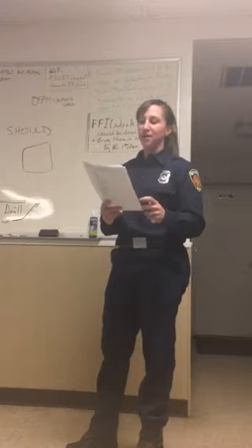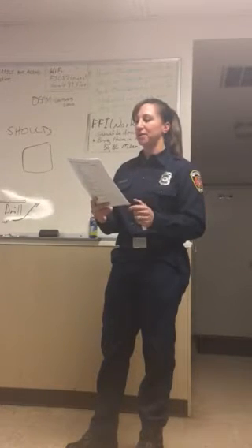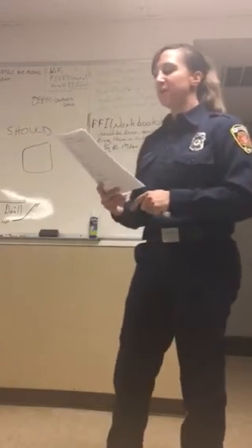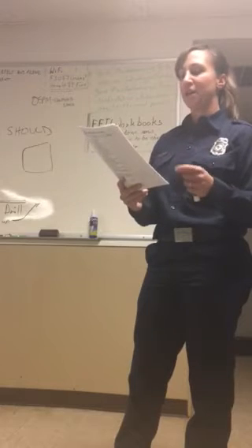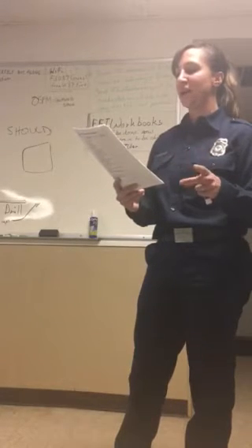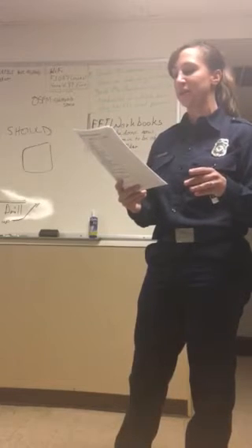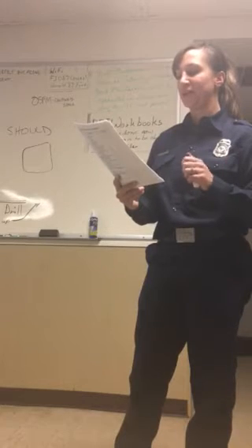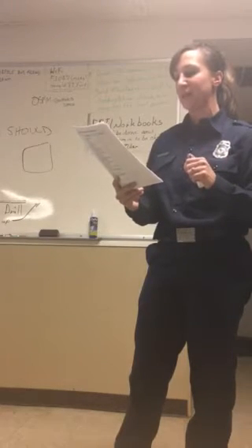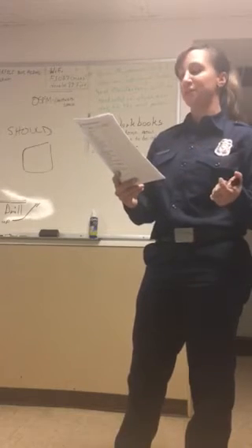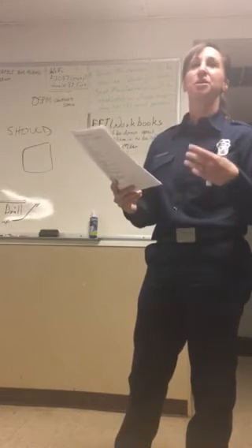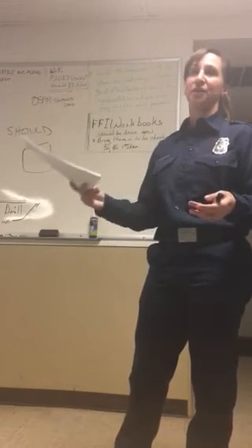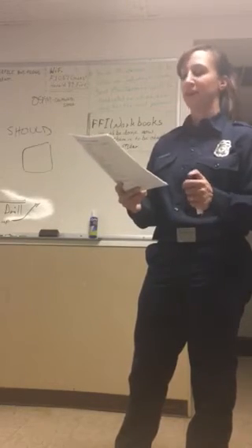It is regulated through Cal OSHA that you monitor in the following order: you do your oxygen, you do your LEL, and then you do your toxicity. On your piece of paper where you're gathering all your data, you want to record location, time, testing results, the name of the person doing the testing, and the time the results came in. You want to note any IDLH, which is immediately dangerous to life and health, what can cause immediate collapse, and things that could have transient effects 12 to 72 hours later. Just because you're exposed to something doesn't mean you'll see it right away. It could take 12 to 72 hours for things to accumulate in your system.